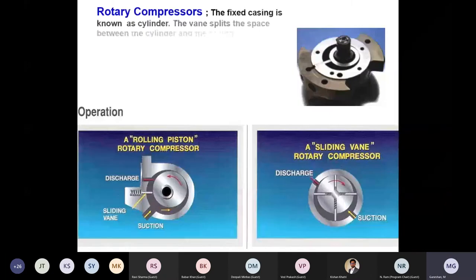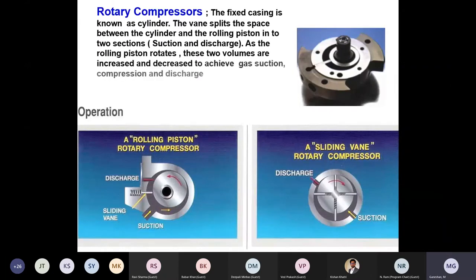Another type we have is the rotary compressor. Here you have a fixed casing known as a cylinder. Then the vane splits the space between the cylinder and the rotating piston into two sections, that means suction and discharge. As the rolling piston rotates, first suction happens, then the gas is drawn in, then it goes into the discharge side. So this is how it works, with single vane and multi-vane types. This is called a rotary compressor.